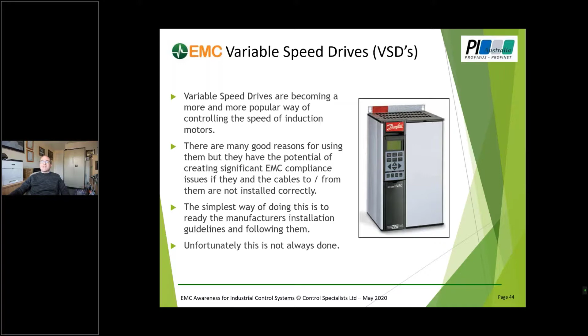Basically, the way in which VSDs, variable speed drives, work is they use pulse width modulation. Our 50-60 hertz supply is rectified internally and smoothed to some voltage, between 600 and 800 volts, depending on the supply voltage. If we were to put a scope across the terminals of the motor, we would not see a sine wave. What we'd see are on-off pulses, maybe not as neat and square as this, but basically a square wave nonetheless, using pulse width modulation.